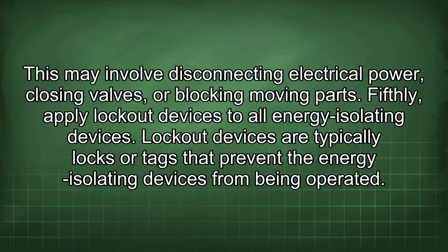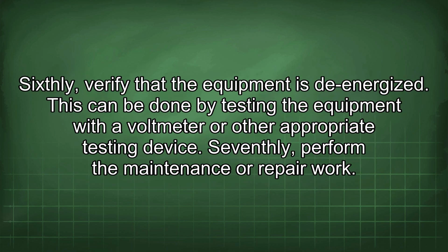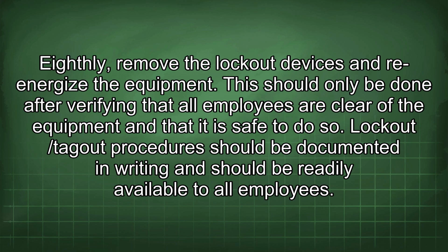Fifthly, apply lockout devices to all energy isolating devices. Lockout devices are typically locks or tags that prevent the energy isolating devices from being operated. Sixthly, verify that the equipment is de-energized. This can be done by testing the equipment with a voltmeter or other appropriate testing device. Seventhly, perform the maintenance or repair work. Eighthly, remove the lockout devices and re-energize the equipment. This should only be done after verifying that all employees are clear of the equipment and that it is safe to do so.